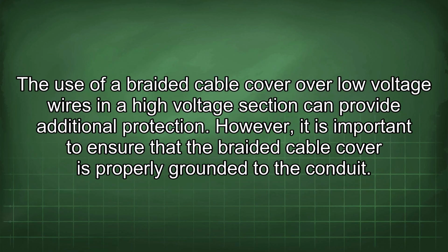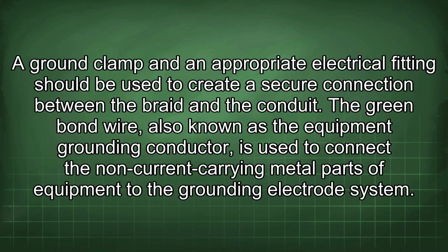The use of a braided cable cover over low voltage wires in a high voltage section can provide additional protection. However, it is important to ensure that the braided cable cover is properly grounded to the conduit. A ground clamp and an appropriate electrical fitting should be used to create a secure connection between the braid and the conduit.